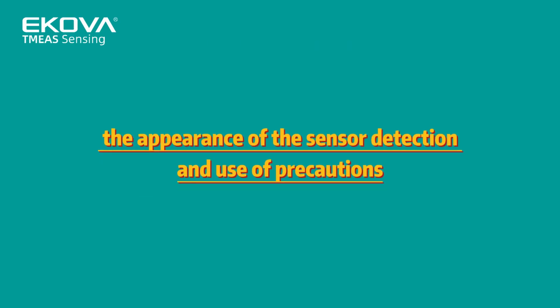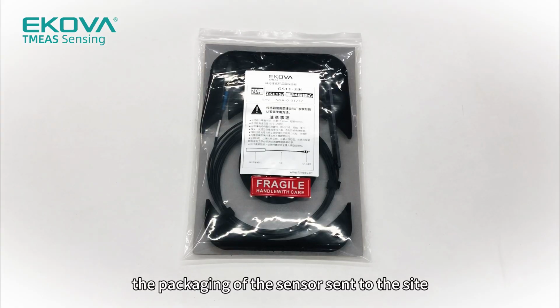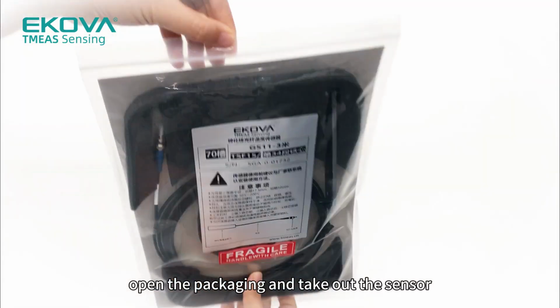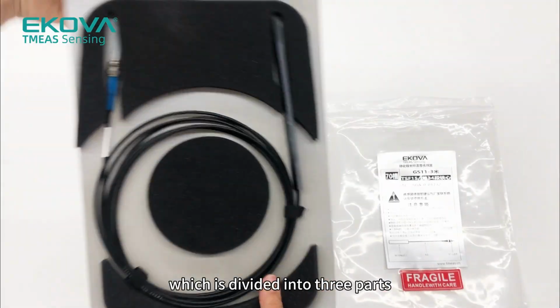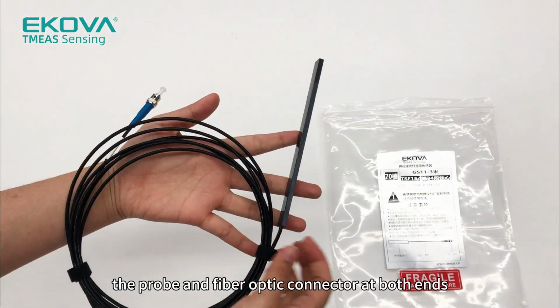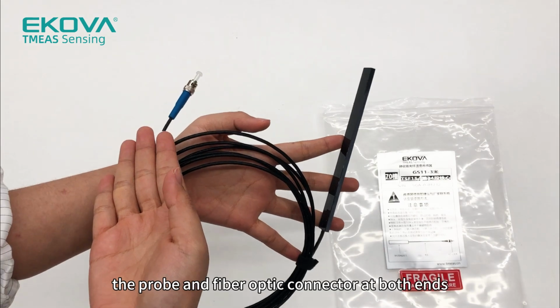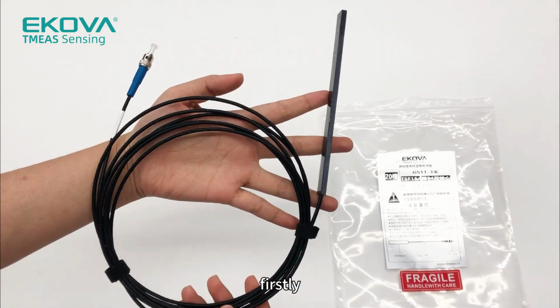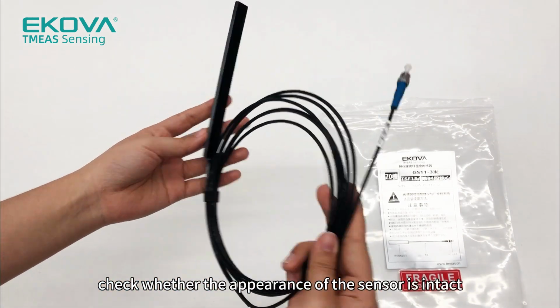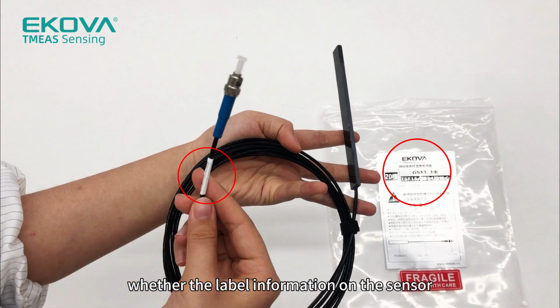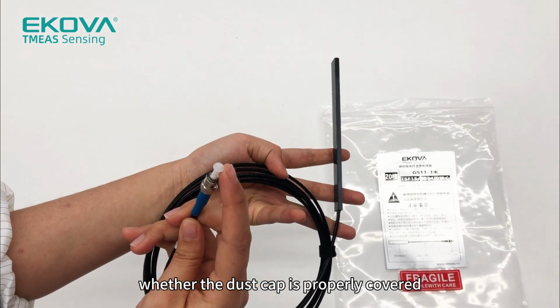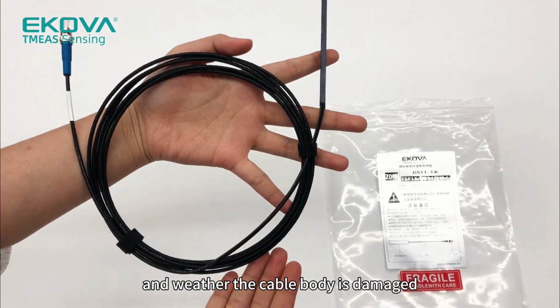First of all, the appearance of the sensor detection and precautions for use. The packaging of the sensor sent to the site is as follows. Open the packaging and take out the sensor, which is divided into 3 parts: the probe and fiber optic connector at both ends, and the fiber optic cable in the middle. Firstly, check whether the appearance of the sensor is intact, whether the label information on the sensor matches the content on the outer packaging bag, whether the dust cap is properly covered, and whether the cable body is damaged.